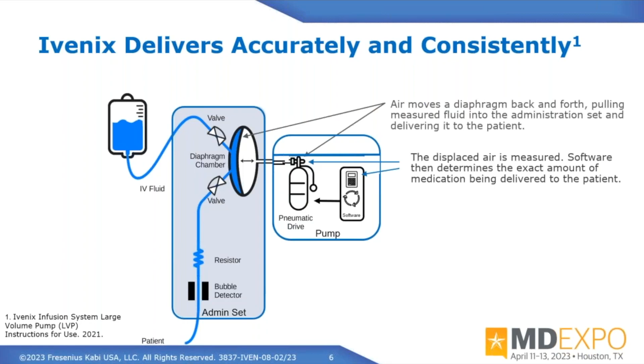Temperature, real world conditions, head height, anything that's affecting an infusion, we've compensated for with that technology. And then where it really matters is those high risk drugs, the half-life, things that we want to make sure we're delivering on time. If we were to forget a roller clamp, which can sometimes happen, the nurse starts the infusion, they go back and the roller clamp was closed and they didn't know it because the device they were using wasn't actively pumping that secondary infusion into the patient.